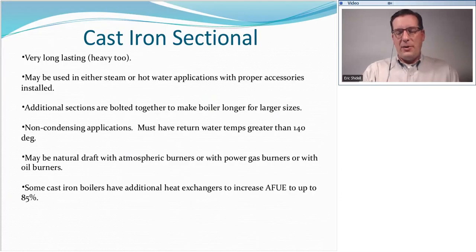To review, cast iron sectional boilers, some of their identifying traits is they last forever. They last a very, very long time. As a result, they're also really heavy. They can be used either in a steam application or a hot water application. In fact, in most cases, the only difference between a steam boiler and a hot water boiler is the steam boiler isn't full up to the water all the way, and the hot water boiler is. Also, there's going to be some additional accessories to make it a steam boiler versus a hot water boiler. But the sections, the cast iron, is the same deal.